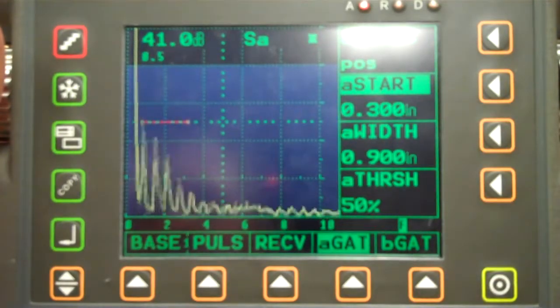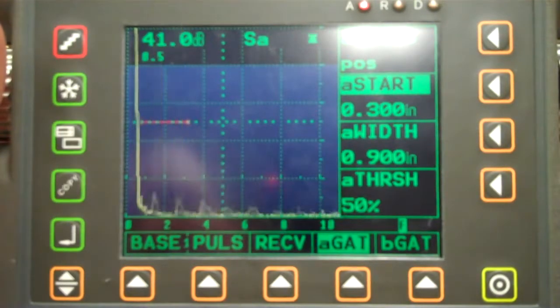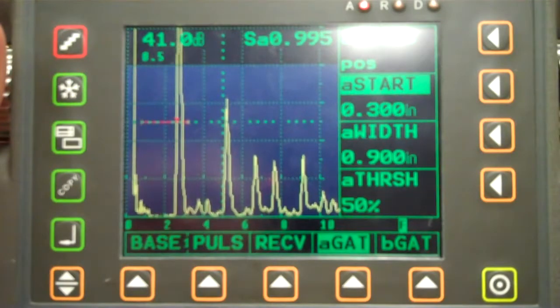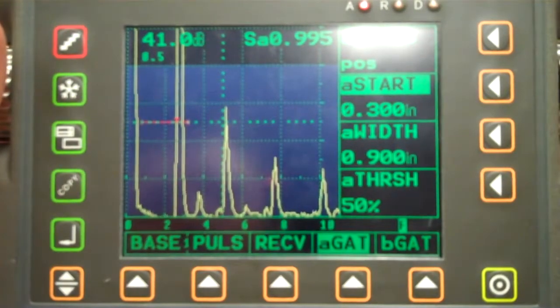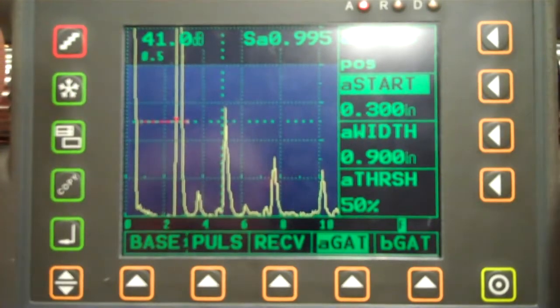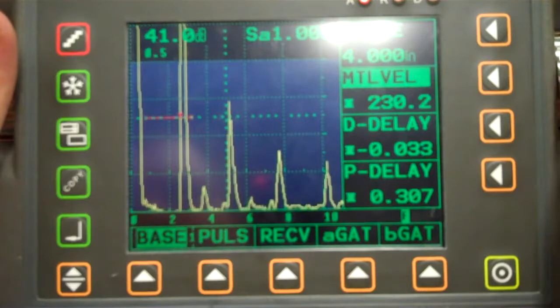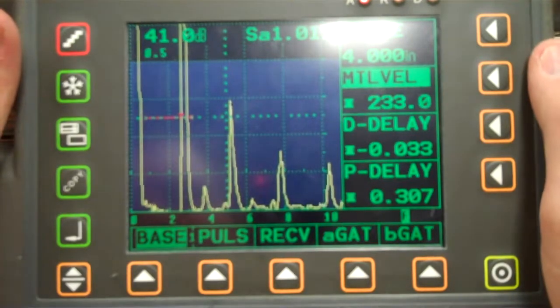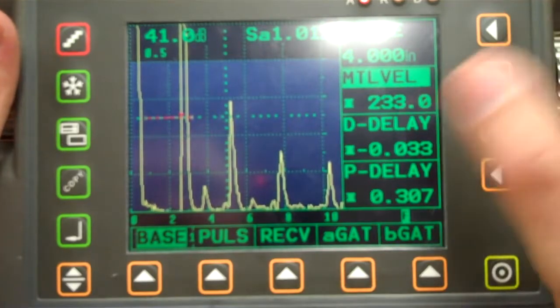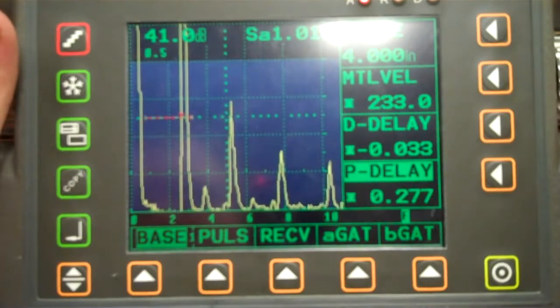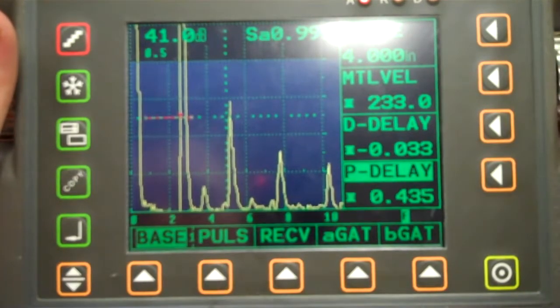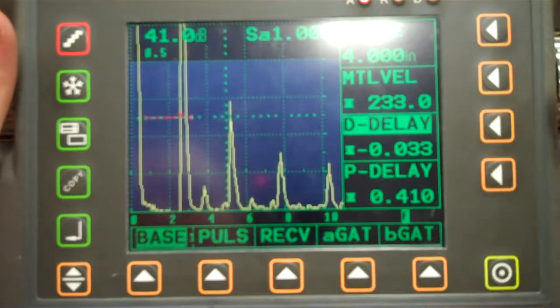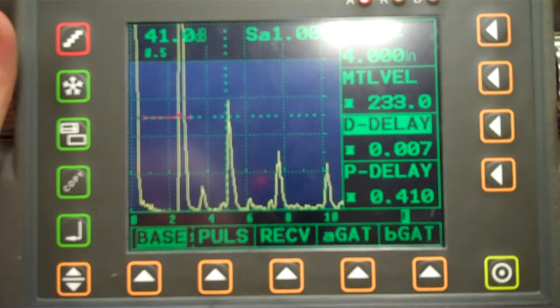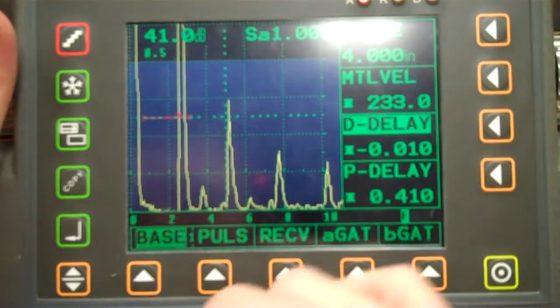Alright, and if I went to 1/4 of an inch, there's my 1/2 inch. It's not necessarily right on. Back to my 1 inch. It's not perfect, but it's close. Within 5/1000ths isn't horrible for thickness testing on a regular old scope here. But I could take my velocity now, crank that back out, and all I'm doing here is just basic calibration stuff. So I'm just messing. I'm just piddling, really, that's all I'm doing. I'll push that in a little bit. Okay, there's 1 inch.